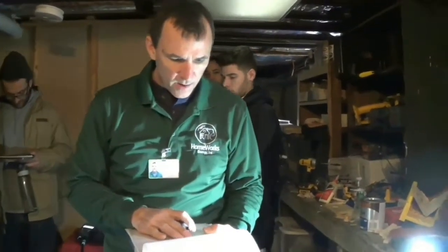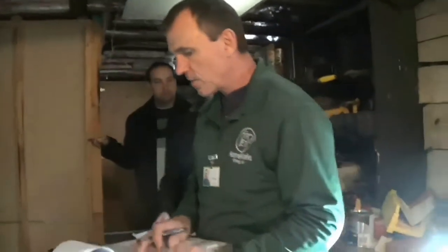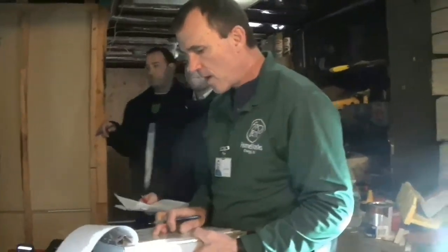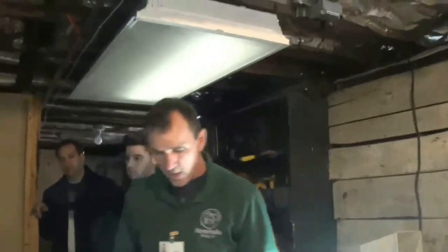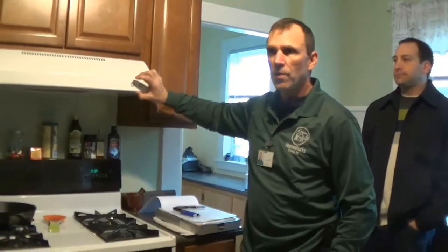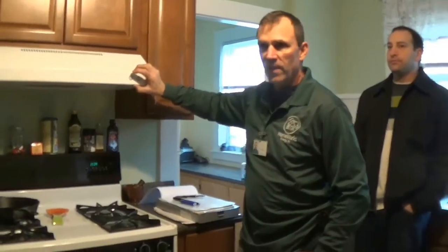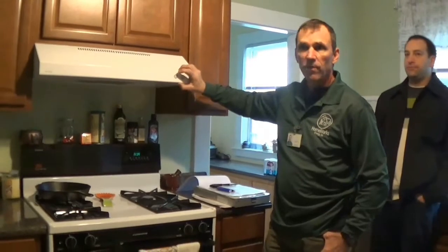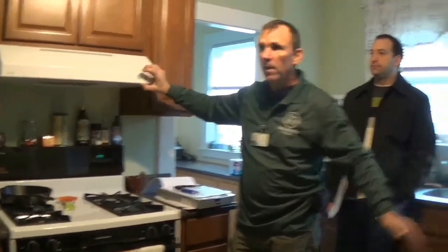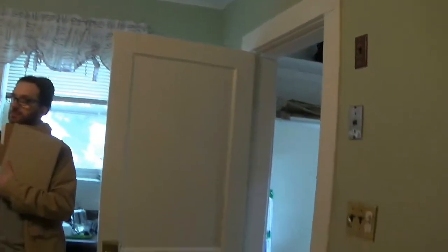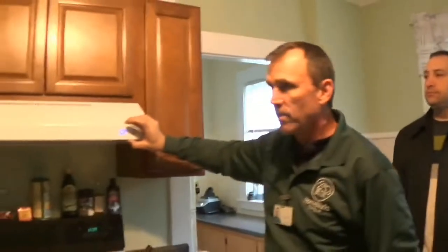And now we're going to go around and we're going to turn on anything that exhausts to the outside, including dryers, bath fan, kitchen fan, range hoods. So we're going to do that. We have gone around and we've made sure that any interior doors that do not have exhaust fans on the other side are closed. We've left the other interior doors open. The basement, the door at the head of the basement stairs and the door to the kitchen here are open because this range has an exhaust fan.